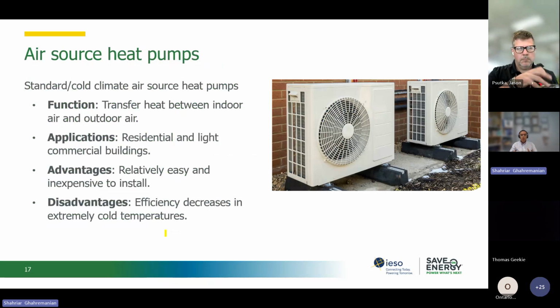There are standard and cold climate air source heat pumps, which we sometimes call CCASHPs. These are also available. They can work down to minus 31 degrees Celsius. They are a little more expensive than a standard one, but they exist and can operate at a high COP, let's say 2 to 3, during very cold days. As I said, they transfer heat between indoor and outdoor depending on the season, and they can be used in residential and light commercial buildings. They are relatively easy to install, with very inexpensive installation.